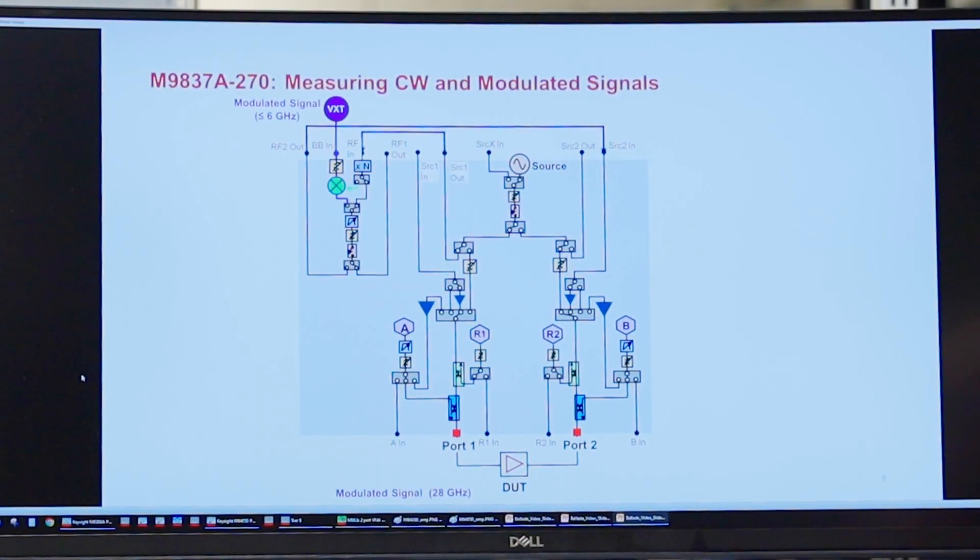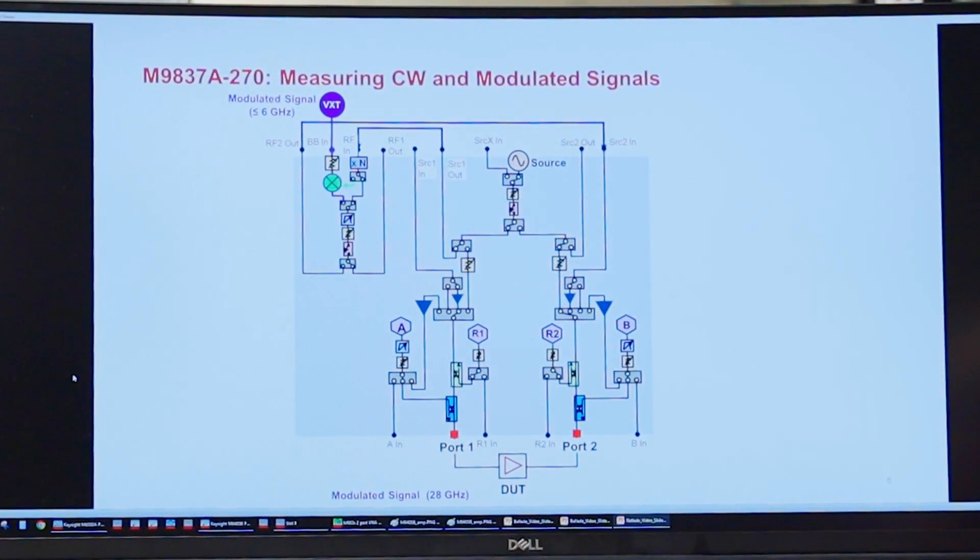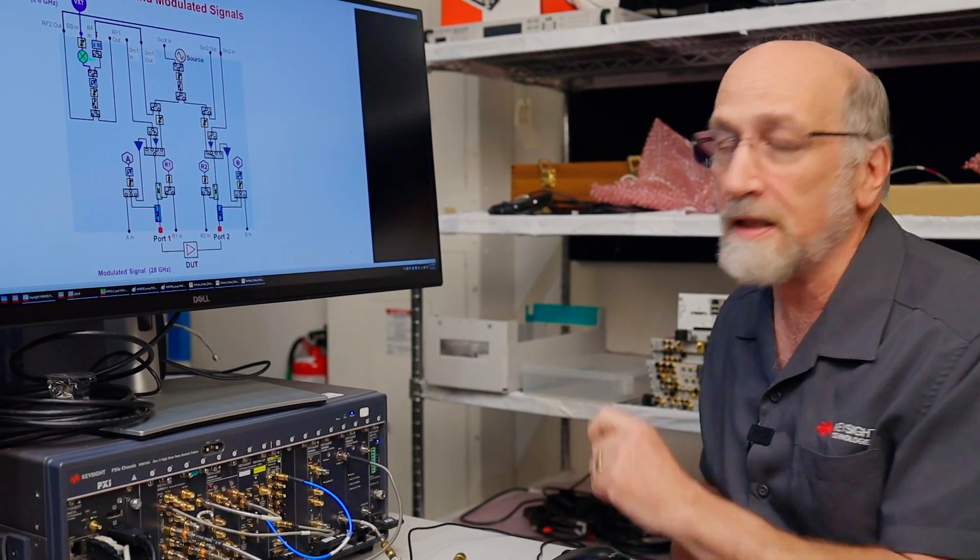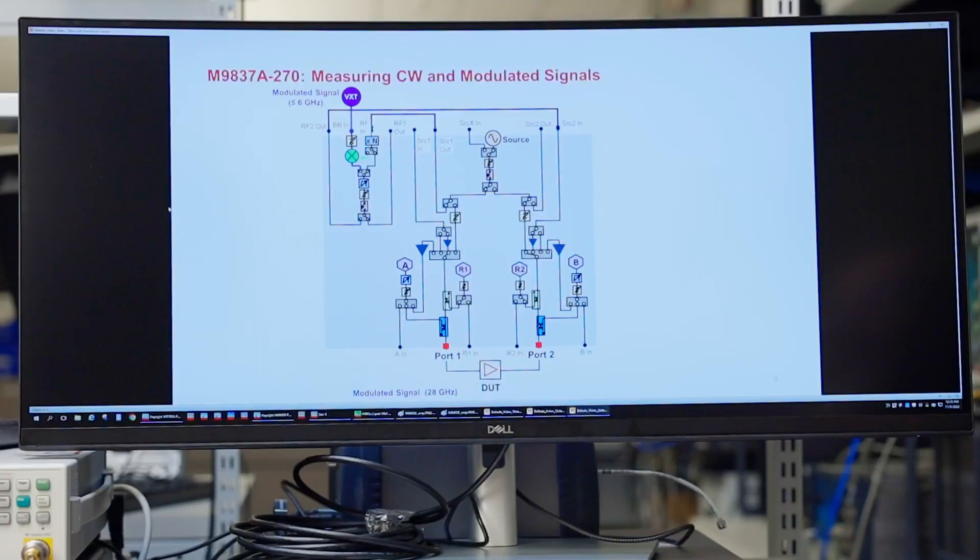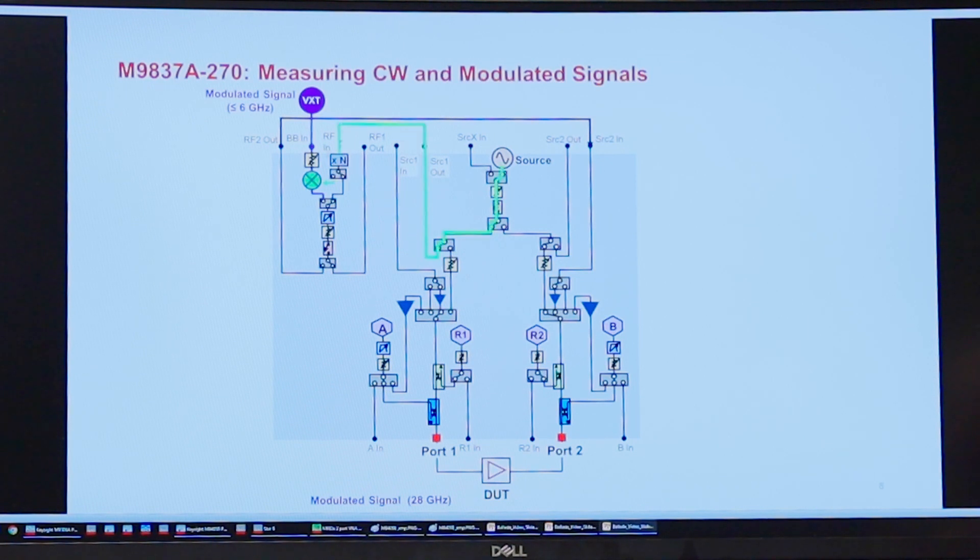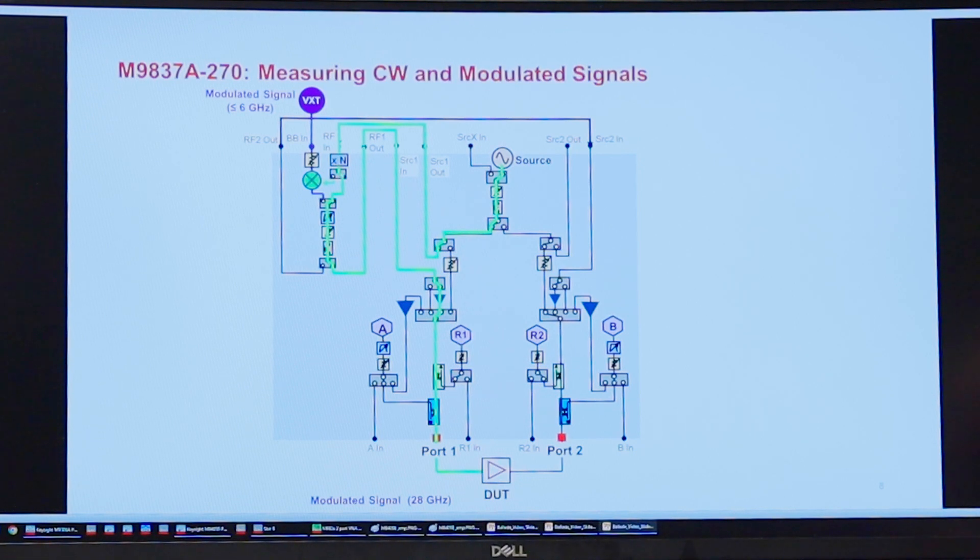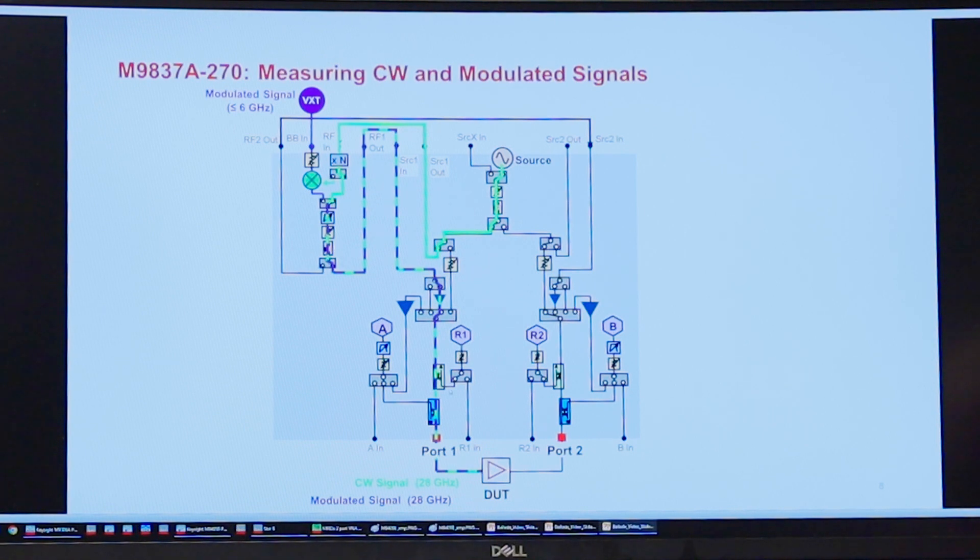We can change the block diagram to do modulated drives using the VXT as a modulation source. So the VXT can produce 6 GHz of modulation, but we want to be at higher frequencies. So internal to the module we have an up converter that gets used to take the source. Normally in a CW measurement the source comes directly out through this doubler. But for modulated measurements we feed the source to this up converting mixer. It comes through filters, attenuators, and pulse modulators to generate a modulated signal at the output. And that's what I'm going to be doing just now.